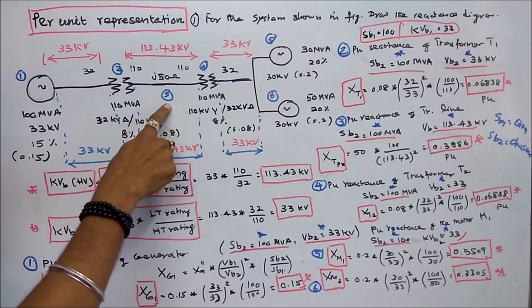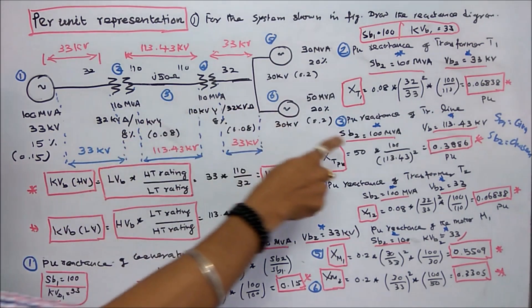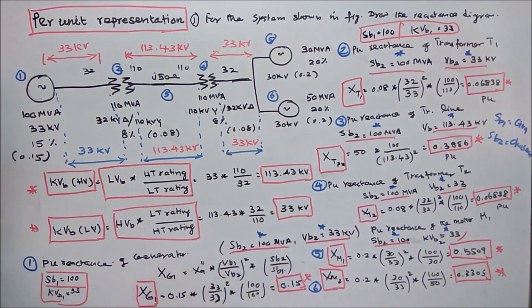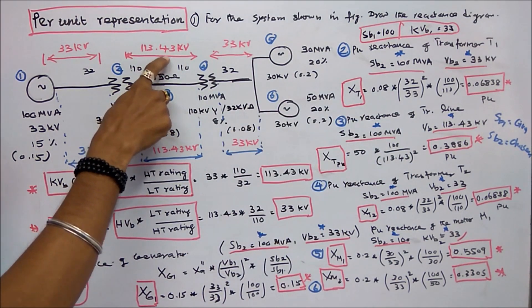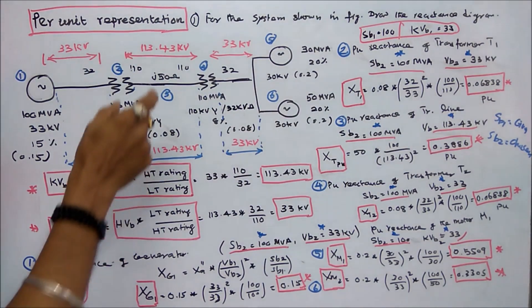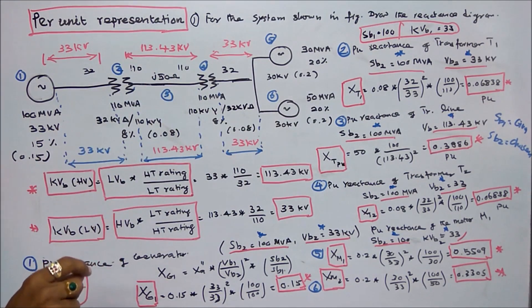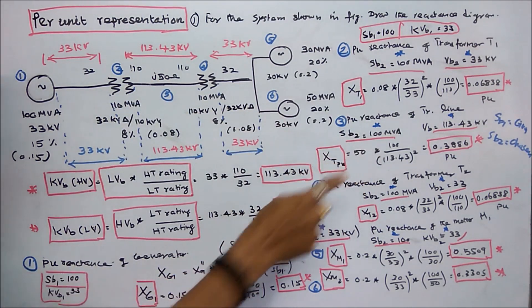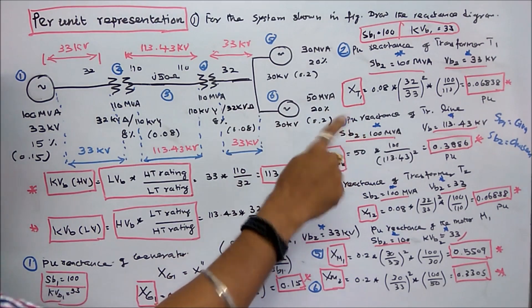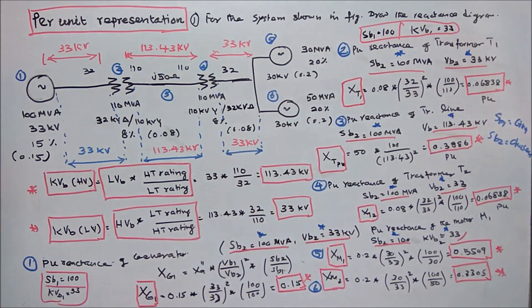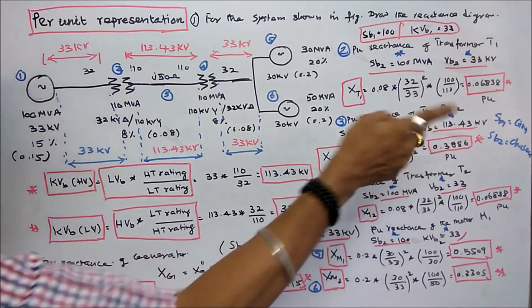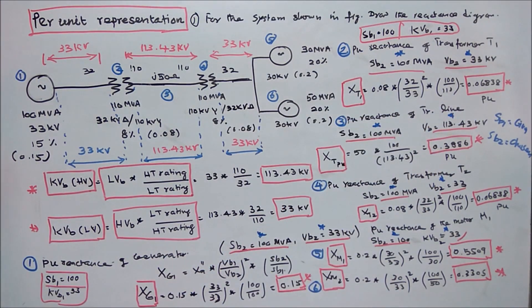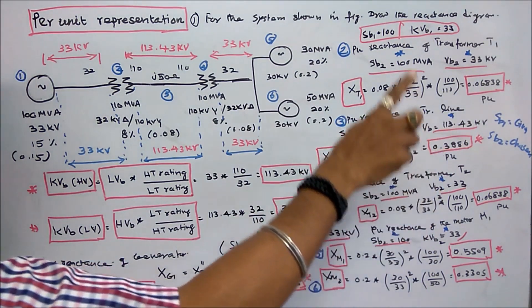The third is per unit reactance of the transmission line. SB2 is 100 MVA and base voltage is 113.43 kV — a very important point. Per unit reactance of the transmission line equals actual reactance value times SB2 divided by KVB2 squared. That is 50 into 100 divided by 113.43 squared, which equals 0.3886.